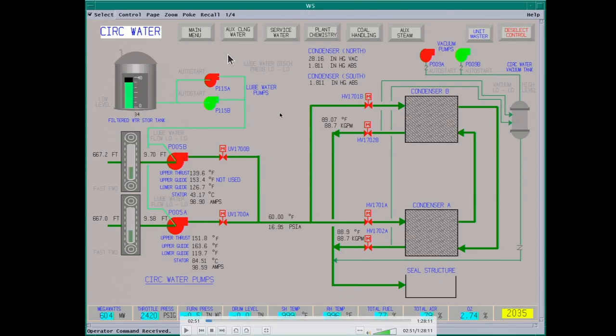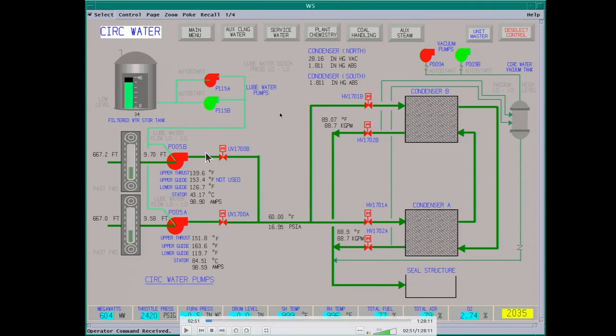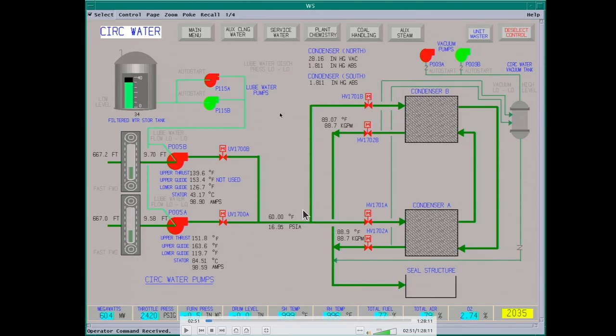This is the circulating water screen. You pump water out of the reservoir through traveling screens through the pumps. You use filtered water for shaft lube water and also to keep dirt out of the shaft. It feeds up to both surface condensers. The water goes in one side, loops back through, and comes out the other — it counter-flows to minimize the heat and provides more of a uniform temperature removal.